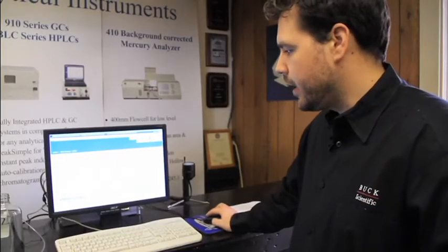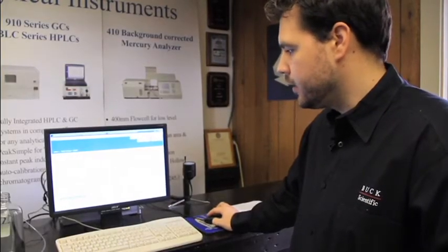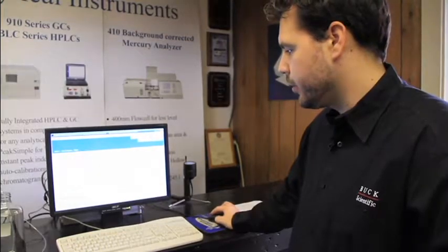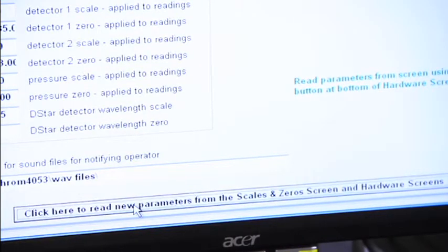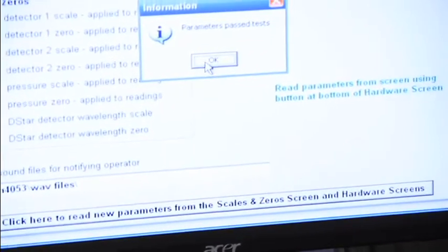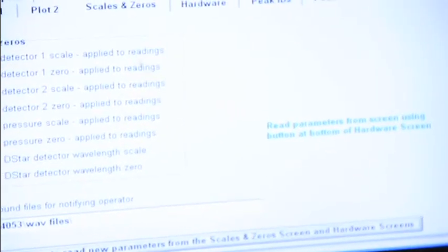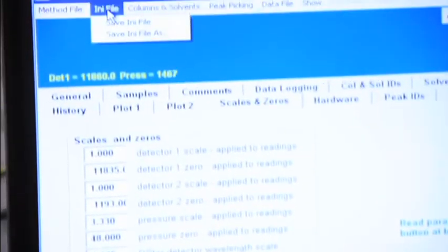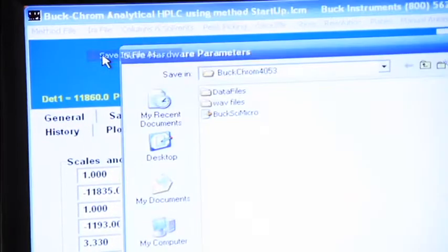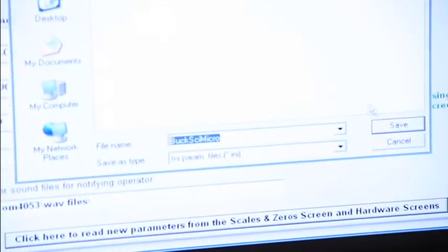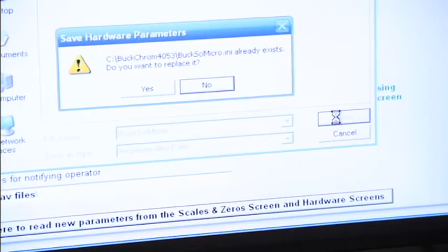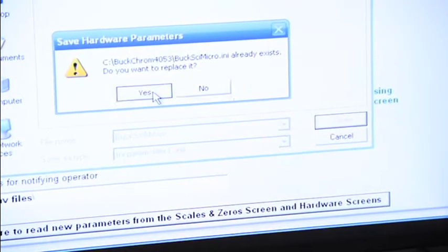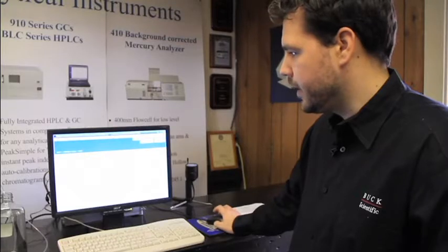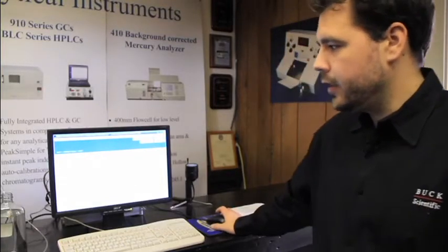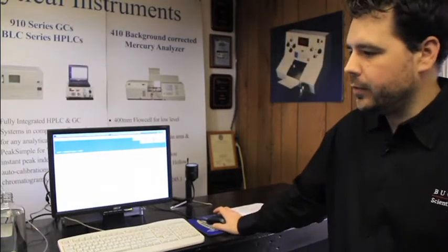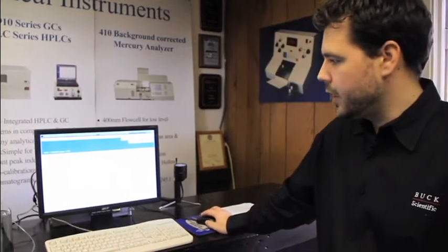Once the values have been entered, click the button labeled "Click here to read new parameters from the Scales and Zero screen and hardware screens." This will bring up a message saying parameters passed the test, and you can click OK. Then go up to INI file and save INI file as Buck-Sci Micro. It should be the default label, and save. Yes, we want to replace it, and now the software and instrument are all set up for running HPLC analyses.